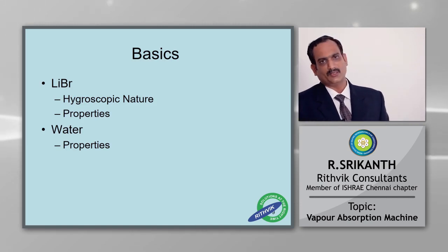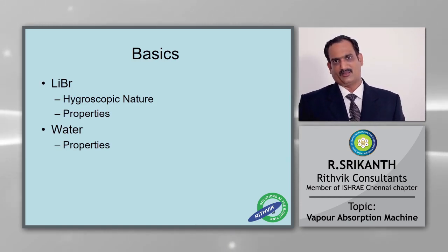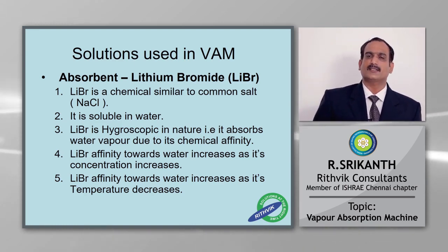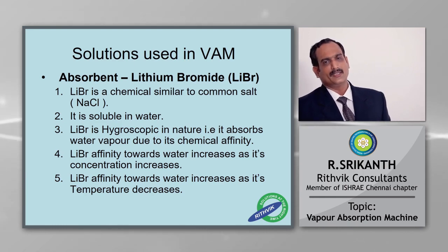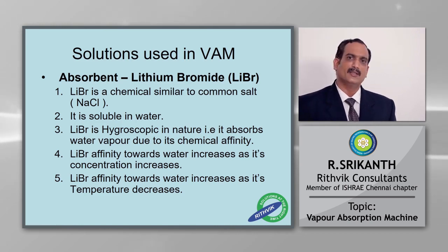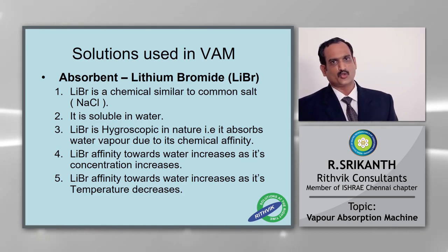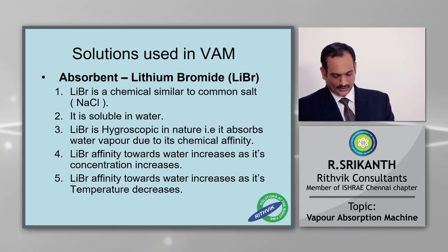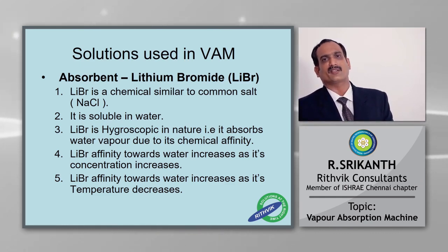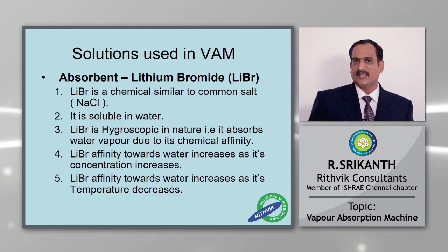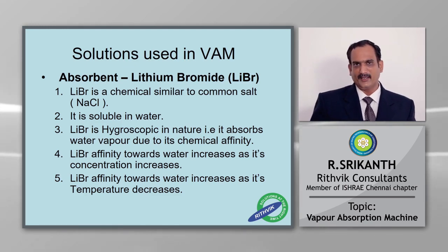The absorption system works with two basic chemicals. We call them chemicals, but one is basically a salt, and the salt is nothing other than lithium bromide solution. Lithium bromide is similar to sodium chloride salt, but the only difference is that lithium bromide is highly hygroscopic in nature. Hygroscopic means it can absorb moisture very easily. Let's say a drop of lithium bromide falls on my skin. I can see the place dehydrate so fast because it absorbs the moisture from the skin instantaneously. So lithium bromide has the property of being highly hygroscopic.